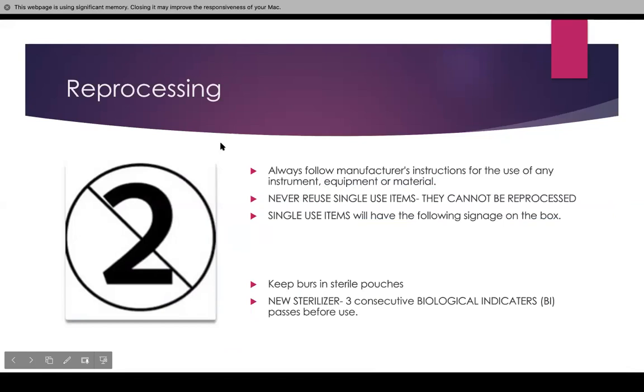For reprocessing, we always have to follow the manufacturer instructions for use (MIFU) for any instrument, equipment, or material. Sometimes our instruments and equipment come with a manufacturer instruction booklet. If we do not find it or happen to lose it, we can always Google the brand or name and write MIFU, and then you will have it for that instrument or equipment.